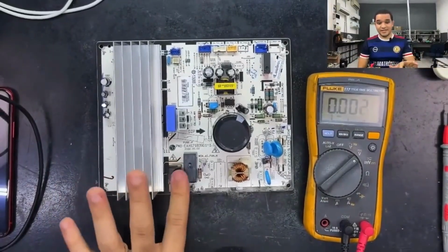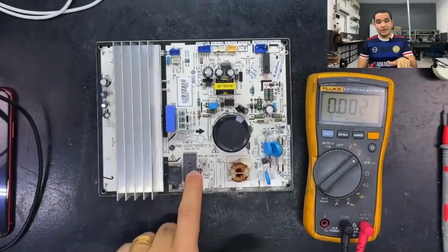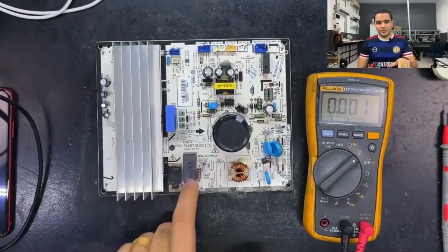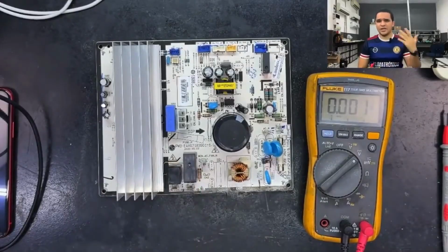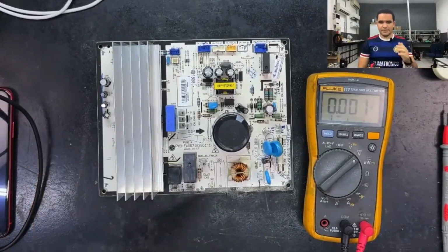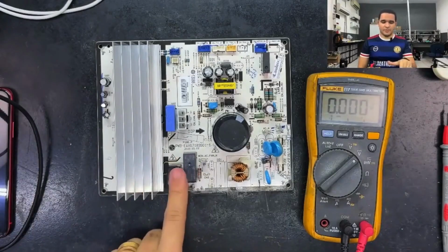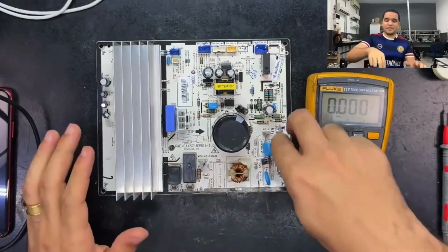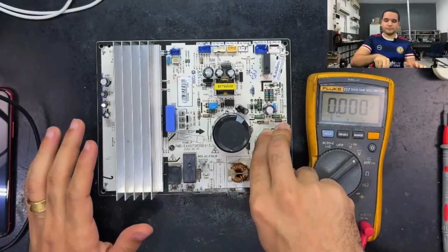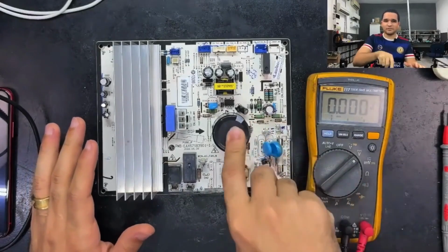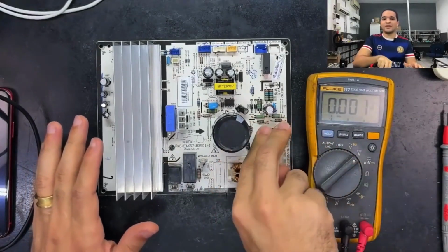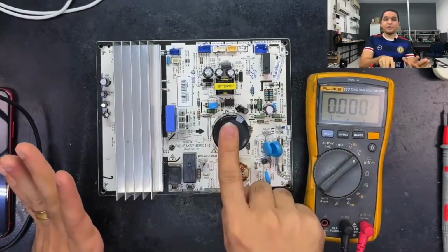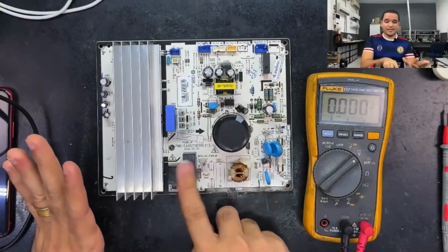If it is heating up, it's because this relay here didn't remove this PTC from the circuit. This relay didn't activate. Or, if it did, it might be faulty. Could be the relay or the circuit activating it. I check if 220V is dropping. If 220V is not dropping, it's not low. Therefore, the capacitor voltage should be high. If there are 209, 210V, 215V, the capacitor should have good voltage. If it doesn't, it's this little circuit here.